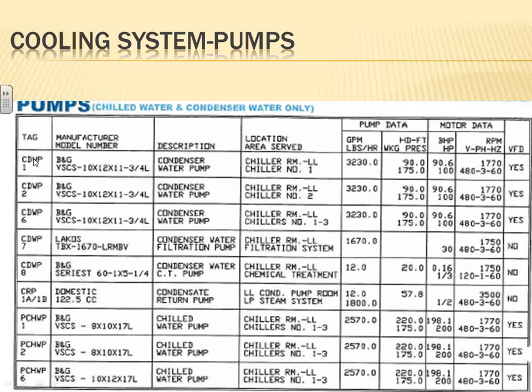My chilled water pumps, and right in here you can see the condenser water. The most important thing about these, electrically speaking, is right here, the horsepower, 100 horsepower. All these are pumps. When we size for pumps, we care less about Article 440, so we don't go to Article 440 altogether. We use 430, and we did what I gave you guys, the sheet that we did last week. So we treat it like any other motor. They're pumps. The voltage is 480, 3 phase system, and it has a VFD specified that's going to be driving that pump. And you can see all this electrical information here.